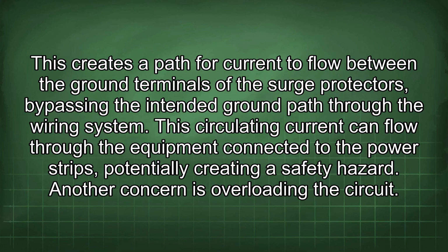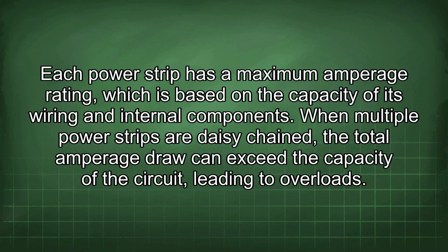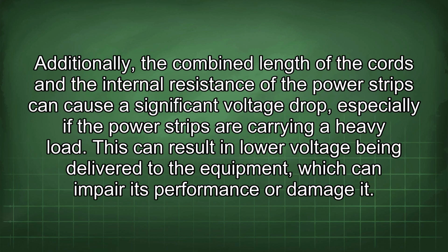Another concern is overloading the circuit. Each power strip has a maximum amperage rating, which is based on the capacity of its wiring and internal components. When multiple power strips are daisy-chained, the total amperage draw can exceed the capacity of the circuit, leading to overloads. Additionally, the combined length of the cords and the internal resistance of the power strips can cause a significant voltage drop, especially if the power strips are carrying a heavy load. This can result in low voltage being delivered to the equipment, which can impair its performance or damage it.